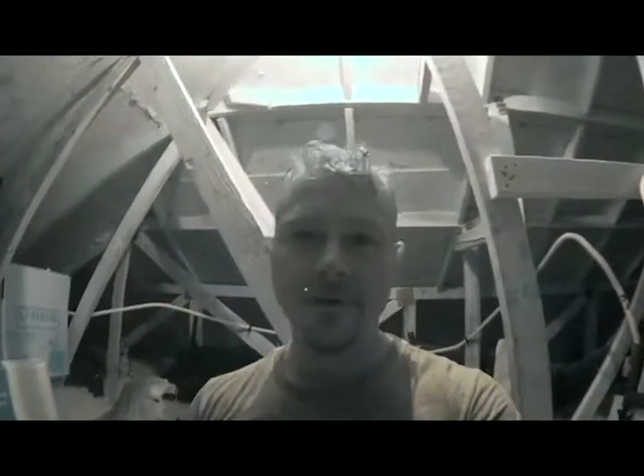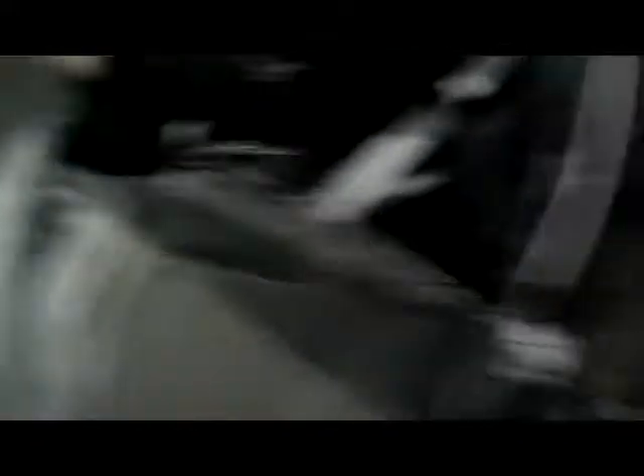After checking the furnace and finding we didn't get any power, I went down to the breaker — the breaker is on. So what we need to do is check the disconnect between the breaker and the furnace. It's a little light switch. To find it, you just follow your power wire from your furnace going right up. On this one we need to remove these two screws. A lot of times this switch will go bad, especially in the attic — these switches basically fall apart.